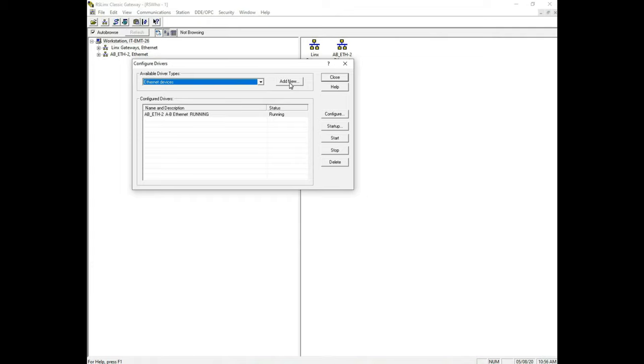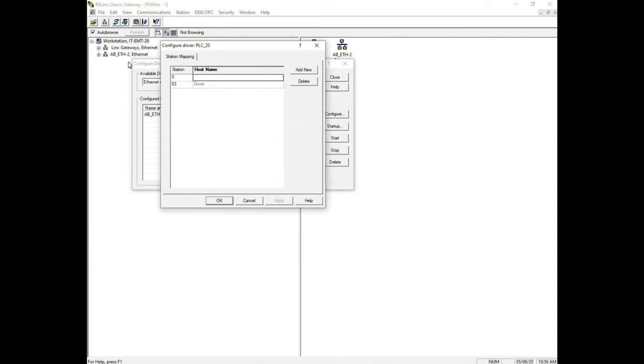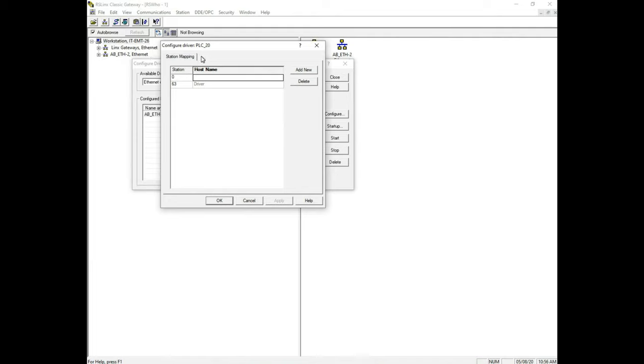When you have an older Ethernet card you have to actually manually put in the IP address so you need to know this. I happen to know the IP address in my lab so I'm going to hit add new. The first box that pops up is something that we need to name. In my PLC lab, the PLC rack that has the older Ethernet card is PLC 20, so I'm just going to name this PLC 20. Remember to name this something that whenever you come back to it you know exactly what you're looking at. This next screen comes up and it tells us we need to map address this PLC, so I know my IP address for my network so I'm going to enter that in here. I hit OK.